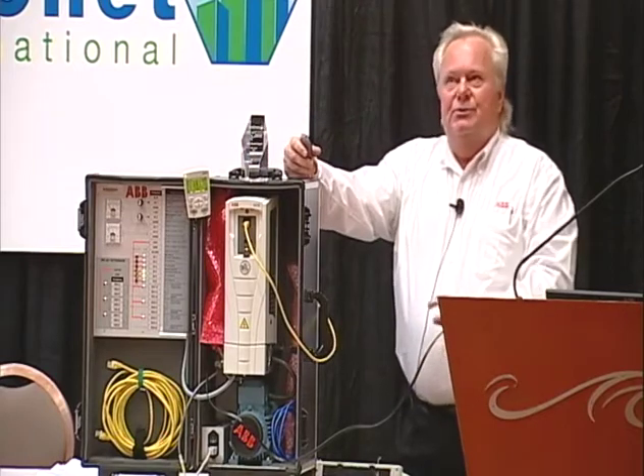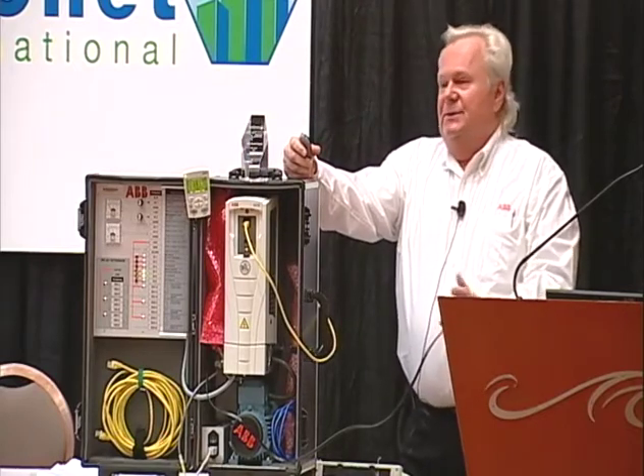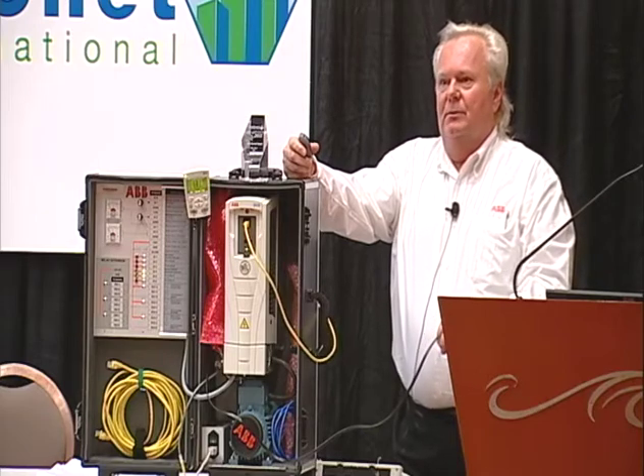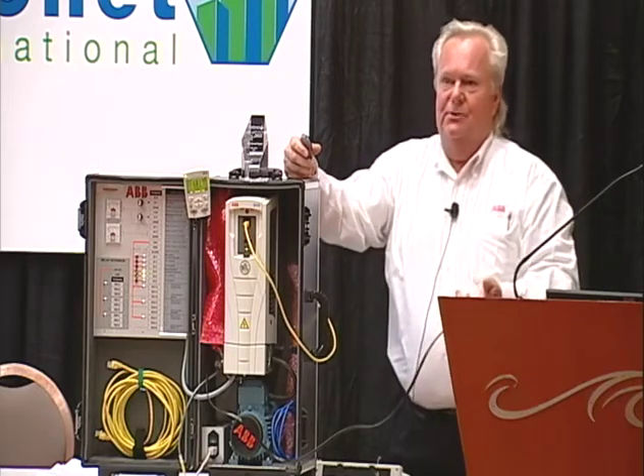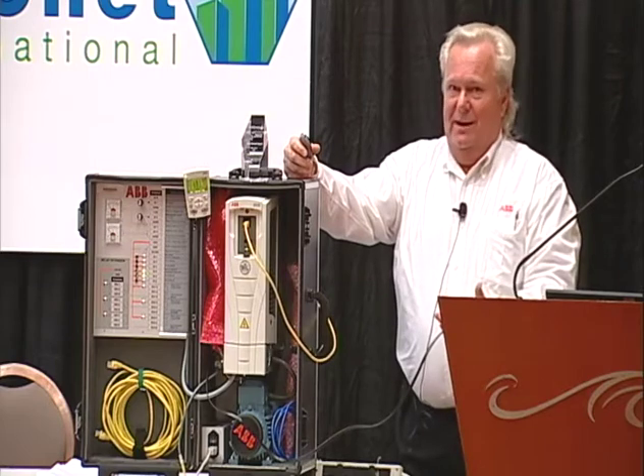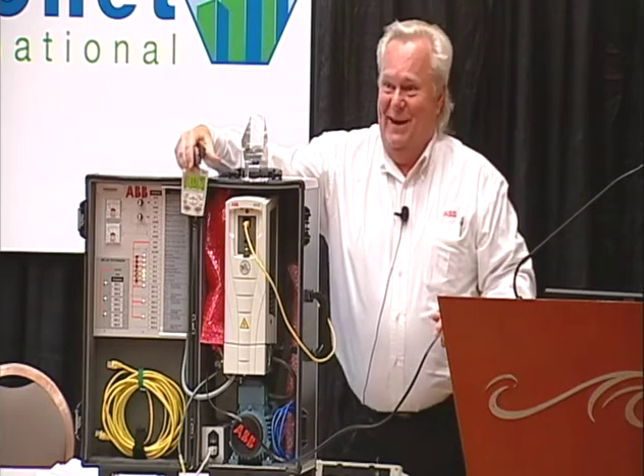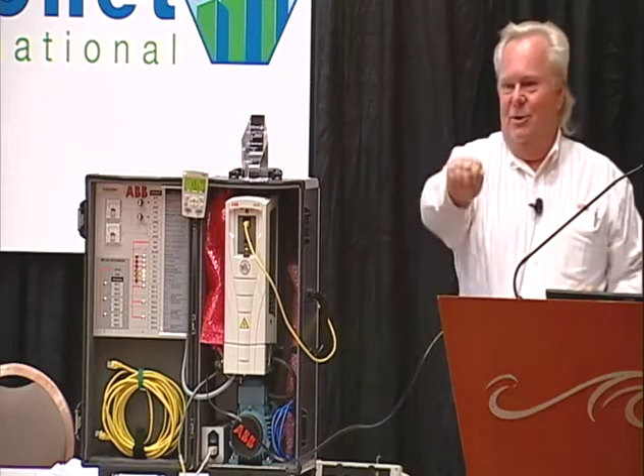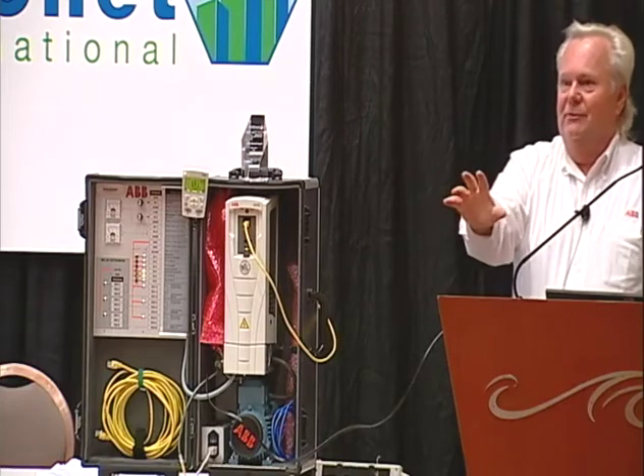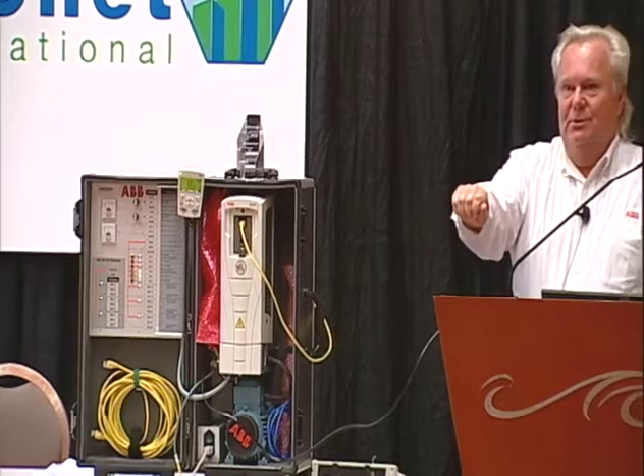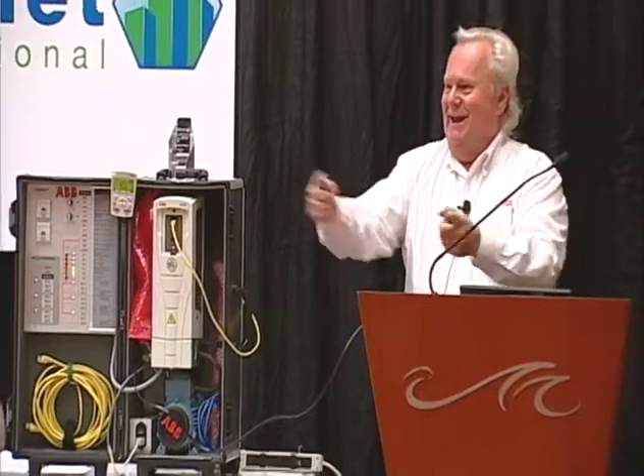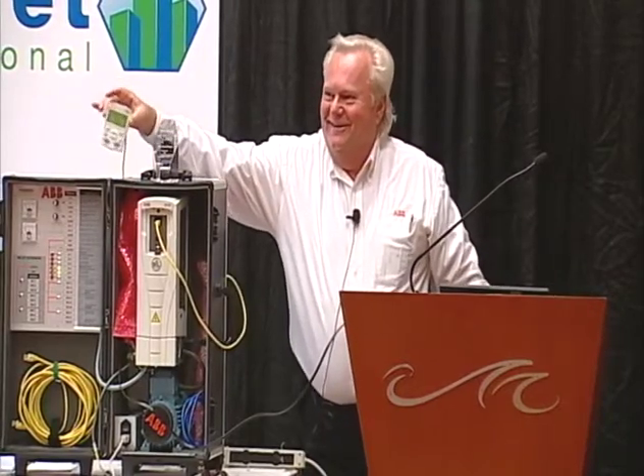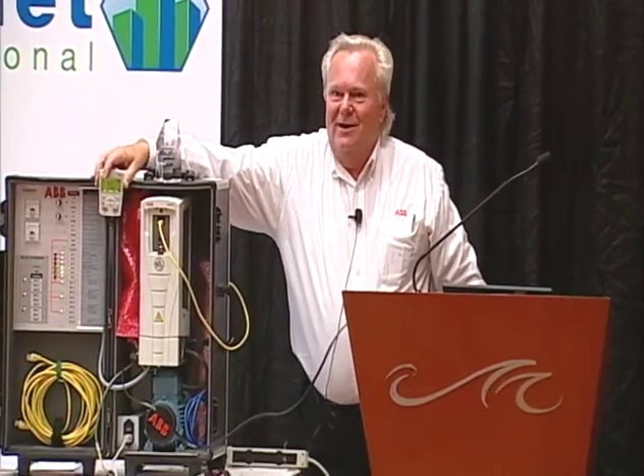Okay, so I just basically insist that the temperature control guys wire that to our system rather than theirs, because there's a lot of different ways to start a modern VFD. There's a hand button here on this keypad. You know, in the old days, we had a hand-off-auto switch on the front of our drives, a regular three-position switch. So it was very easy for the temperature control contractor to cut the wire and put the damper end switch in the hand circuit, so there was no way for an owner to blow his ductwork up. There's no wire anymore. It's all software. It's all in the keypad brains and in the drive brains.